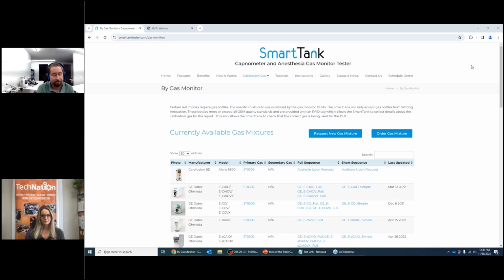Those PMs are a little more complicated because you do have to calibrate for 4 different gases. So they just take a little bit more time, but they still do a leak test and flow test. They actually sometimes have additional pressure tests that are written into them, but it's all stuff the SmartTank will do.